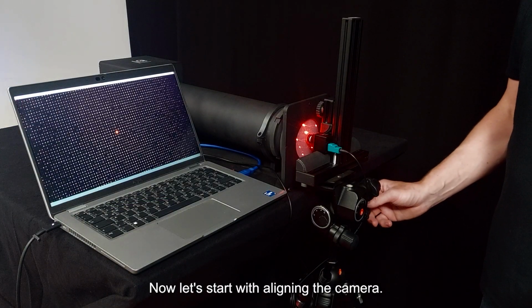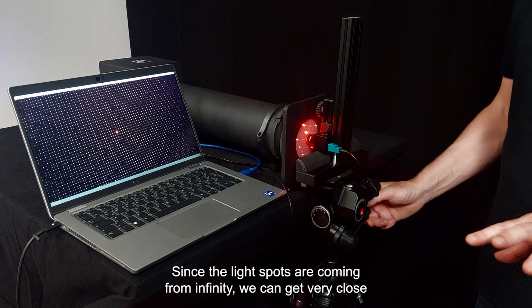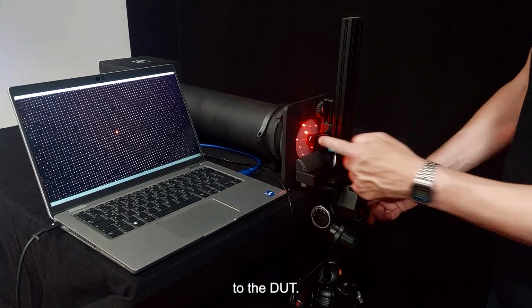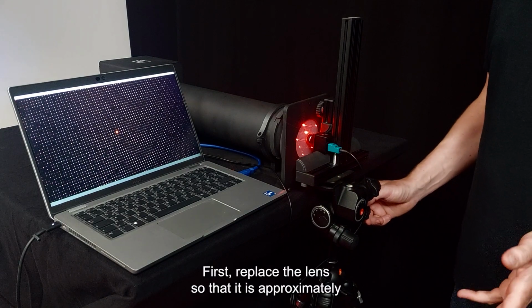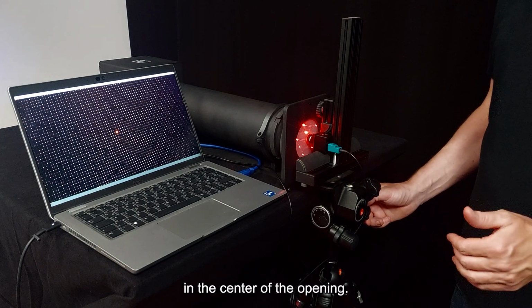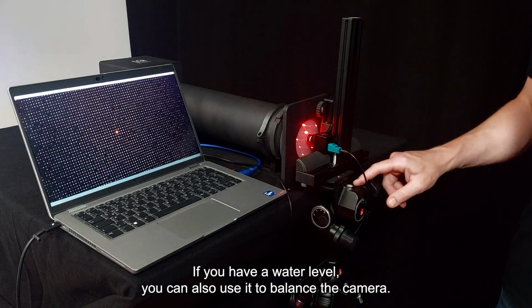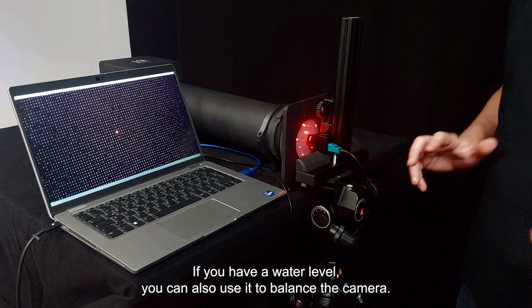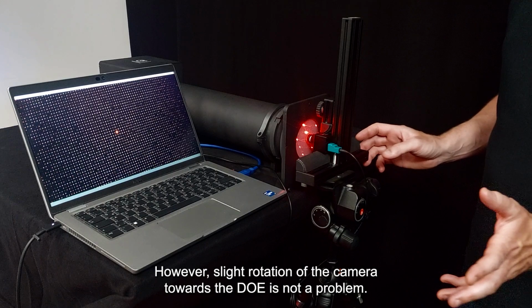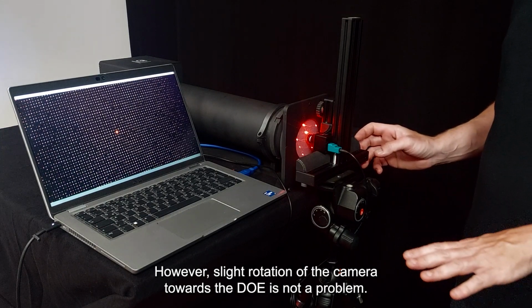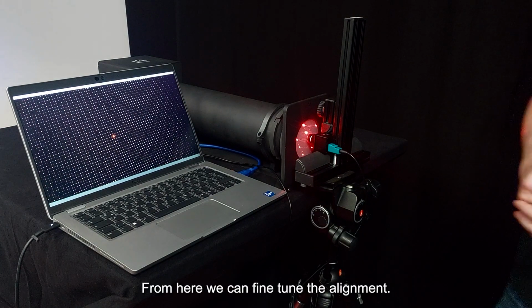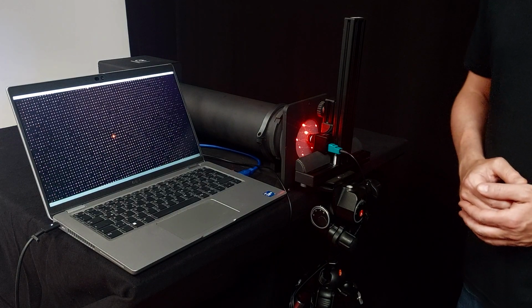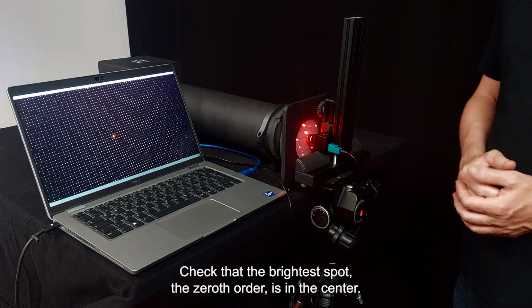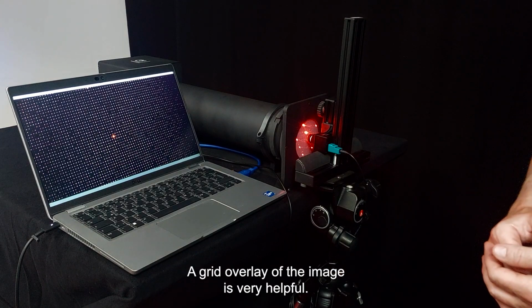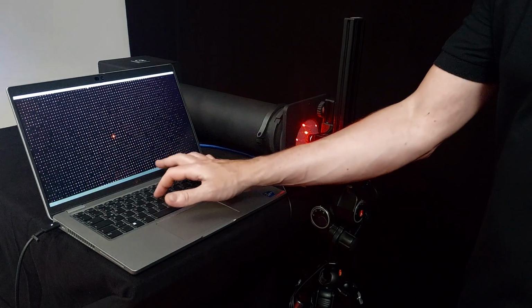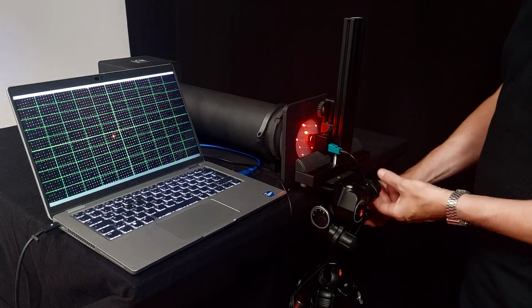Now let's start with aligning the camera. Since the light spots are coming from infinity, we can get very close to the DOE. First, we place the lens so that it is approximately in the center of the opening. If you have a water level, you can also use it to balance the camera. However, a slight rotation of the camera towards the DOE is not a problem. From here, we can fine-tune the alignment. Check that the brightest spot, the 0th order, is in the center. A grid overlay of the image is very helpful.